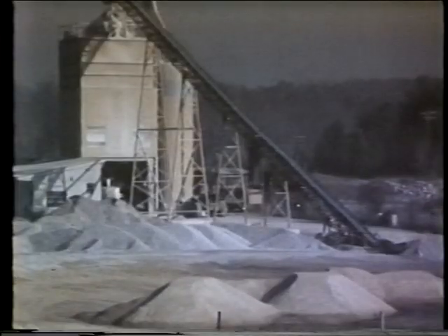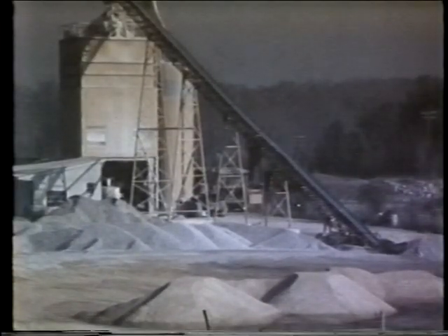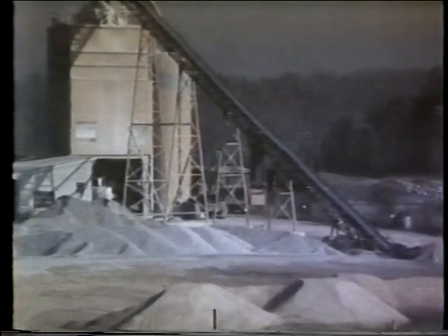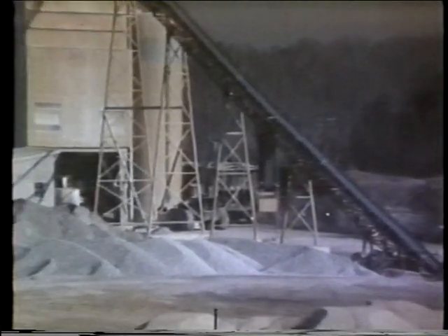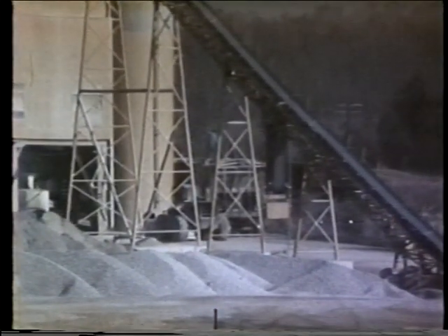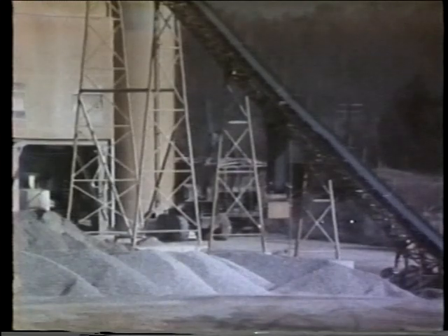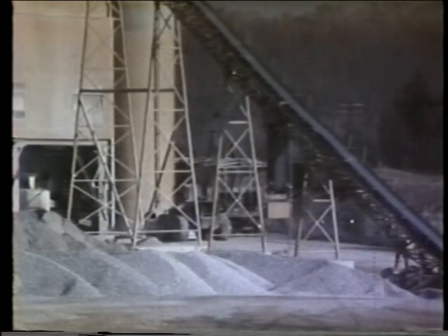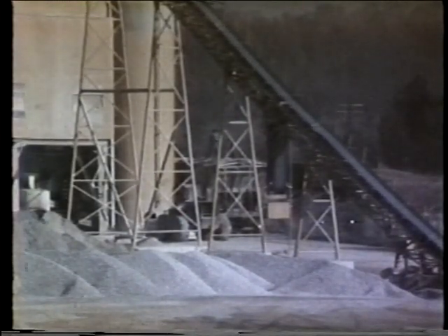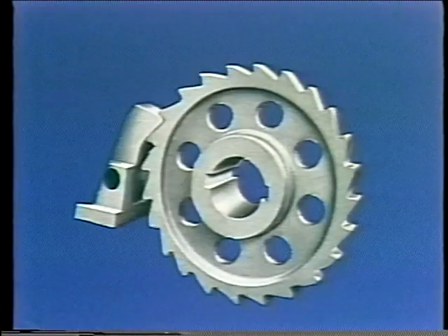Let's take the case of an inclined conveyor that is fully loaded. If the current fails or the powertrain breaks, the material on the belt or in the elevator would then run back and pile up at the base of the unit. Now, this could cause some real problems, if, for example, the conveyor had several tons of sand on it. So normally, these units are installed with a ratchet clutch, which prevents them from running backwards no matter what.